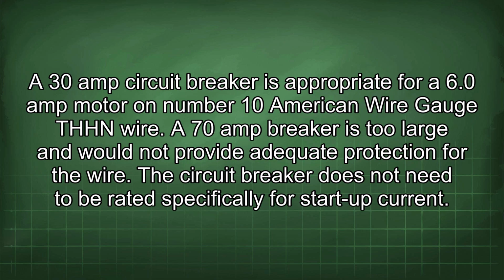A 30 amp circuit breaker is appropriate for a 6.0 amp motor on number 10 American wire gauge THHN wire. A 70 amp breaker is too large and would not provide adequate protection for the wire. The circuit breaker does not need to be rated specifically for start-up current.